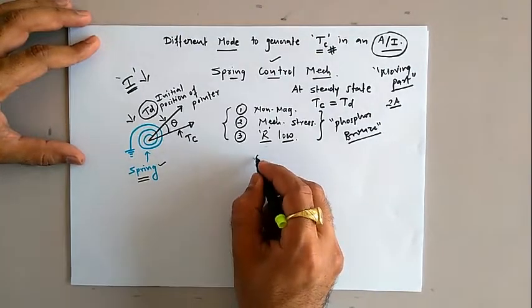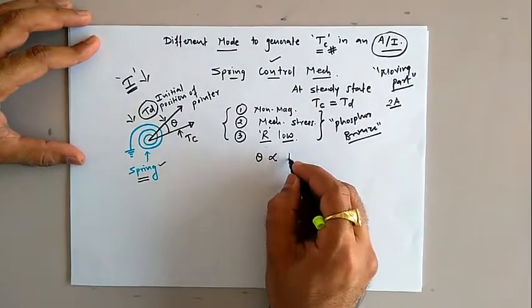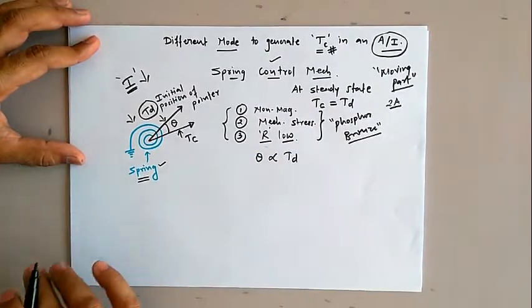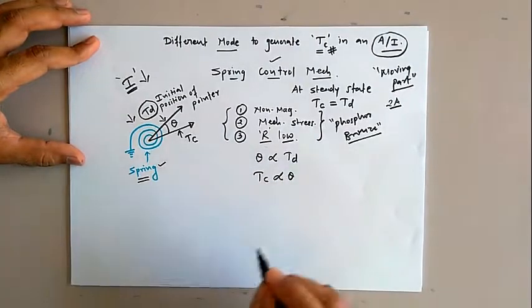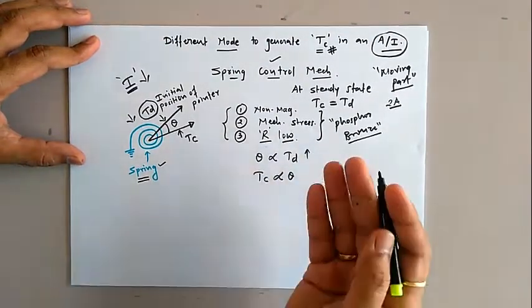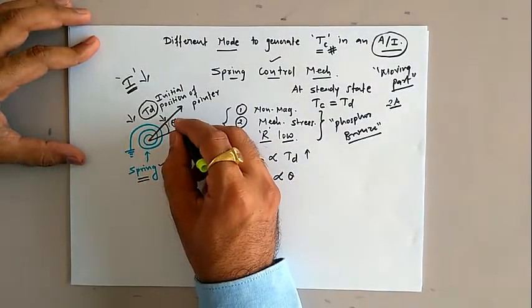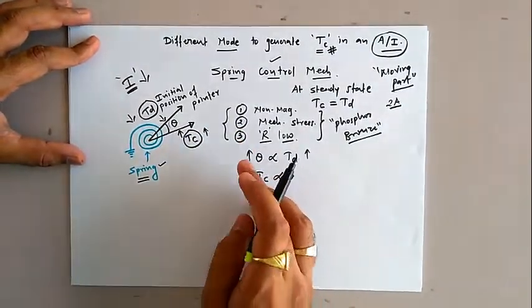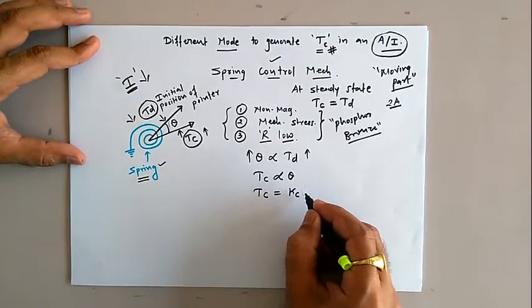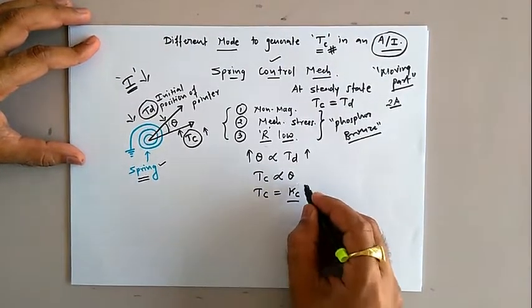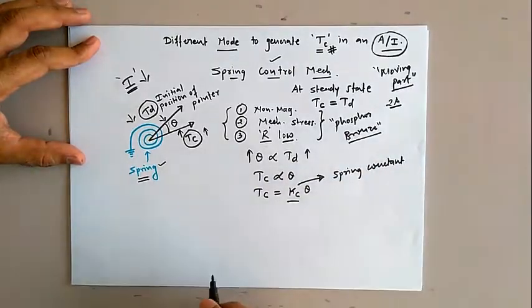Now let us analyze the behavior of this arrangement. The final deflection angle theta is proportional to the magnitude of deflection torque. The controlling torque Tc is proportional to theta, meaning as the deflection torque increases, the angle increases, and correspondingly the opposing torque offered by the control mechanism also increases. So we can write Tc = Kc × θ, where Kc is the constant of proportionality, also known as the spring constant. This is equation number 1.